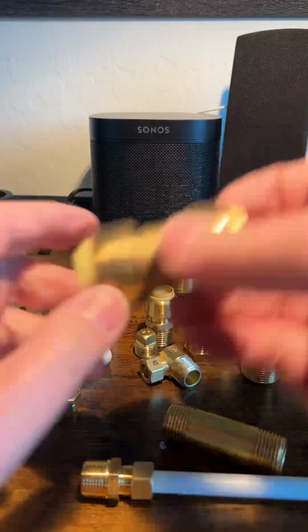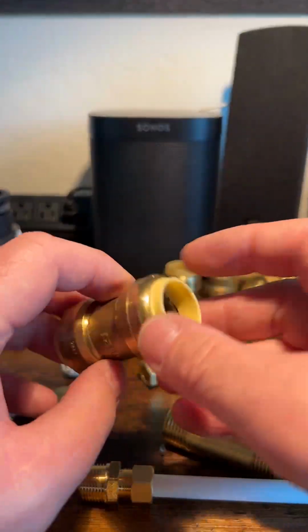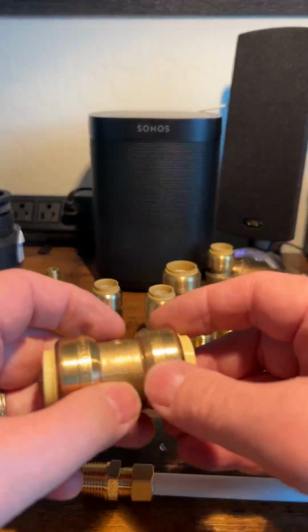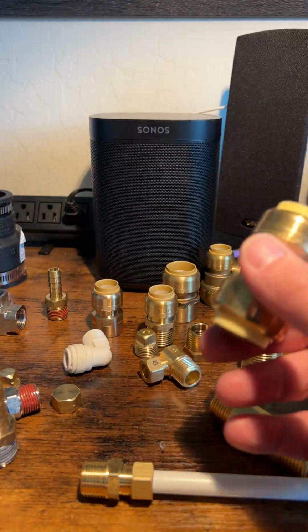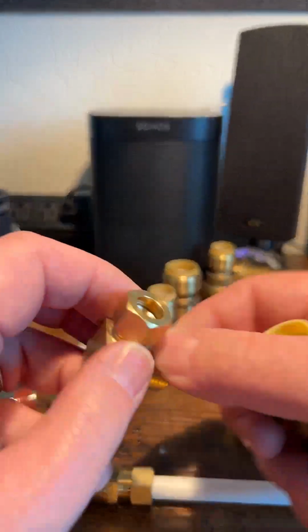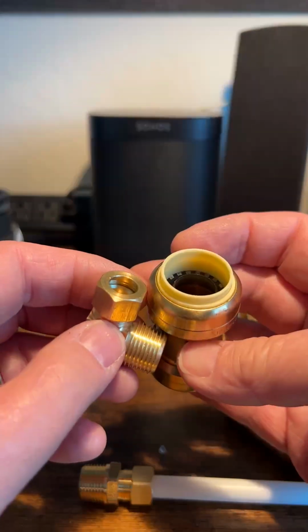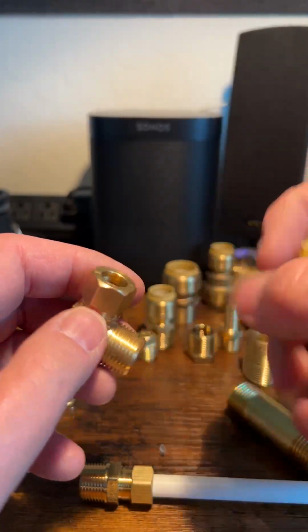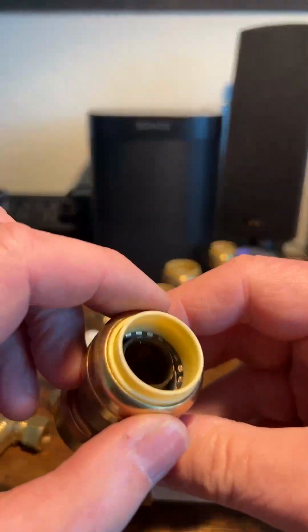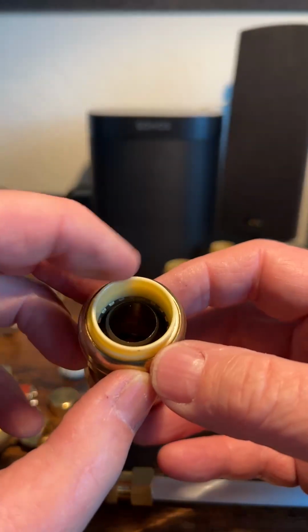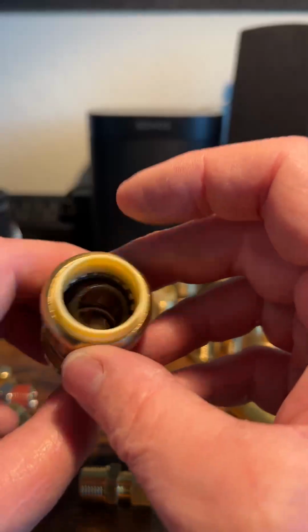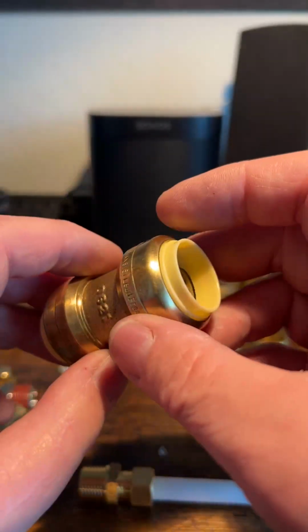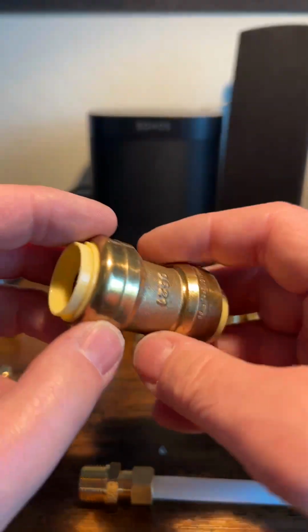When it comes to push fittings, there's all kinds of different types. A lot of plumbers don't like push fittings, but that's kind of the way everything's going. It's easier, it's faster. They don't last as long as a compression fitting will. I can tell you this fitting will last way longer than this type of fitting will. But these have O-rings in them, and the O-ring will degrade over time. The hot water will break it down. So it's not a permanent fixture.